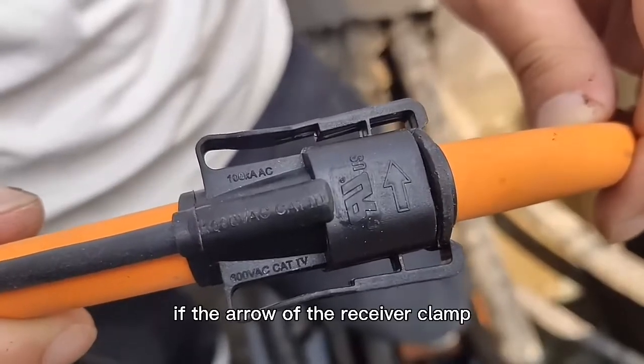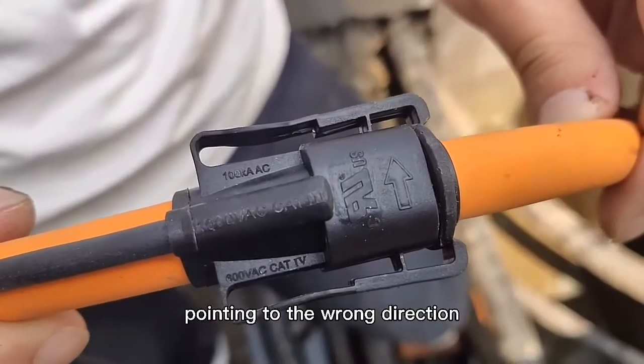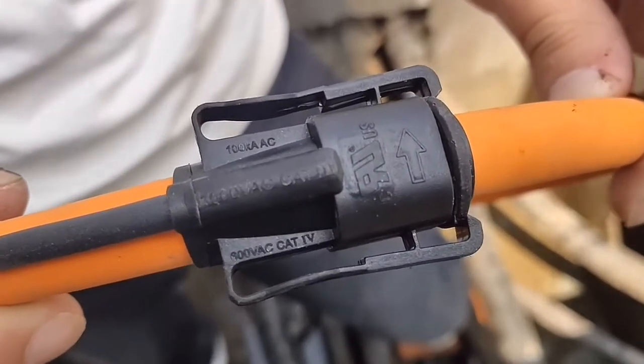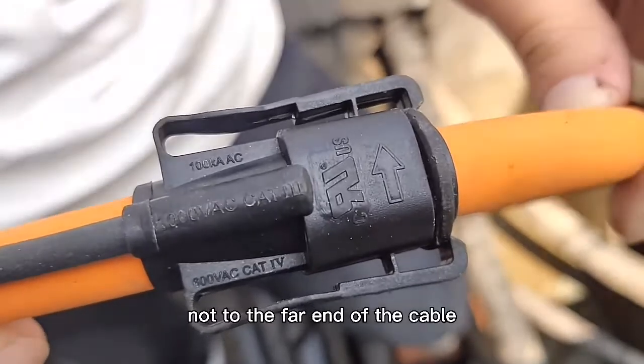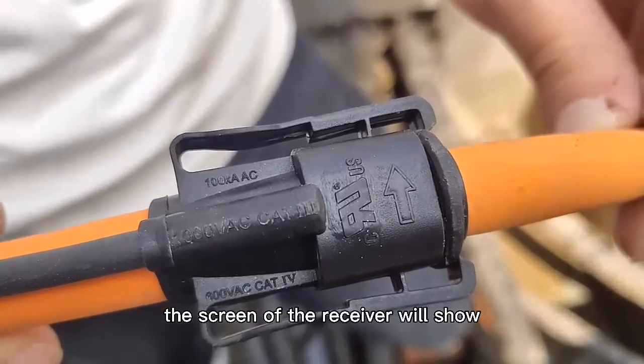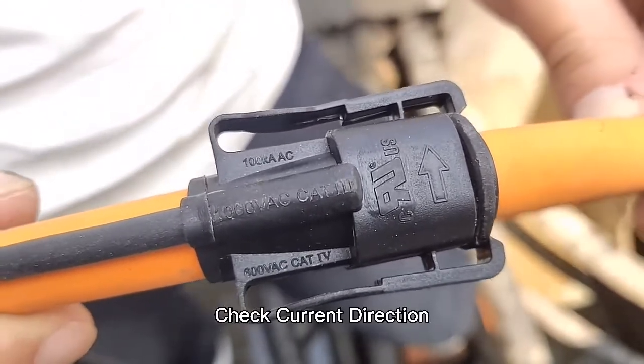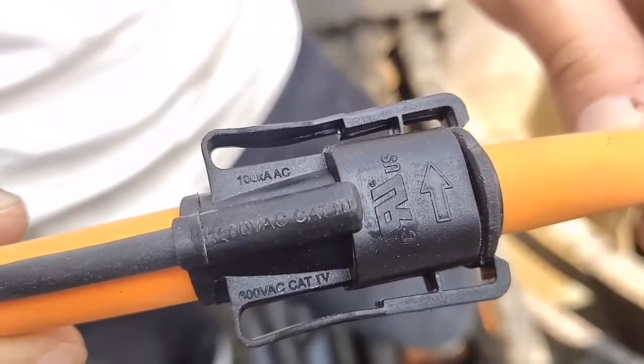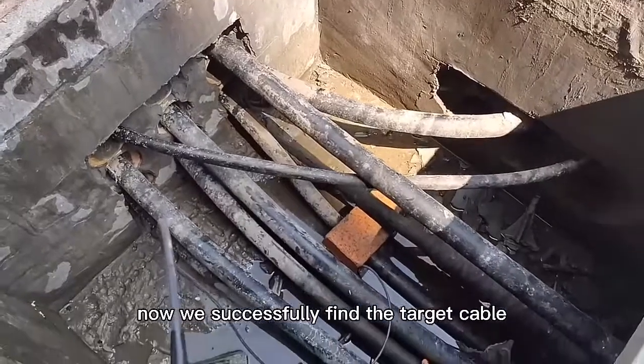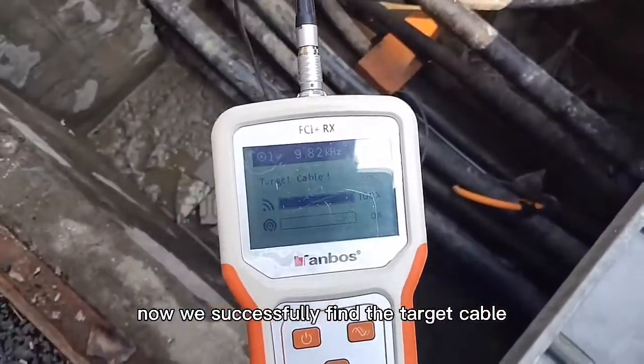If the arrow of the receiver clamp is pointing to the wrong direction, not to the far end of the cable, the screen of the receiver will show check the current direction. Now we successfully find the target cable.